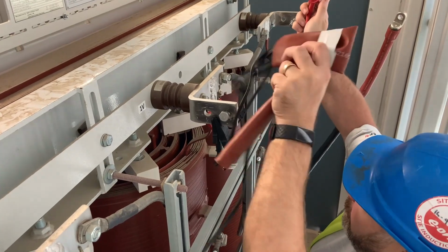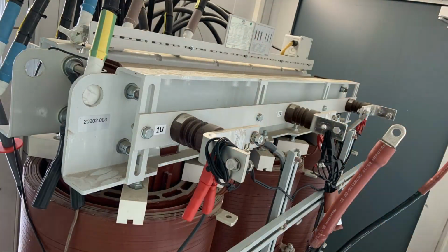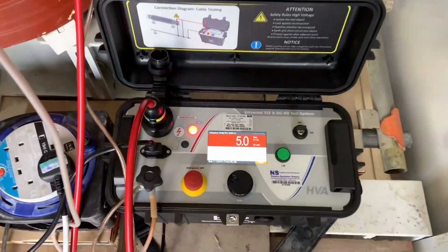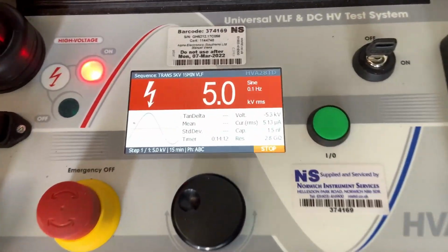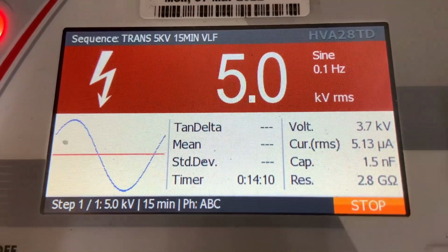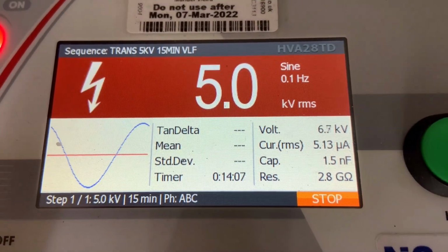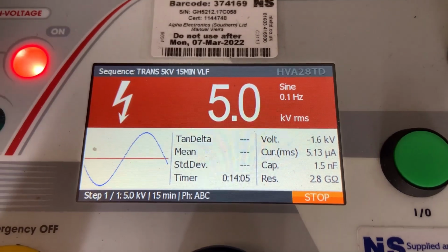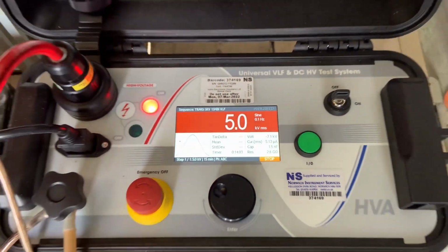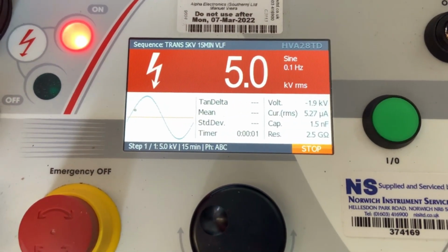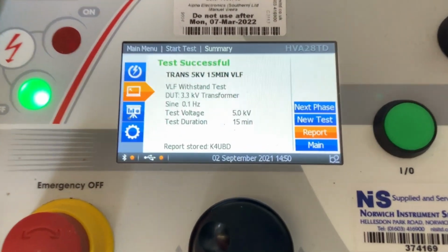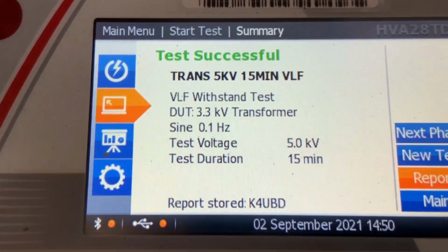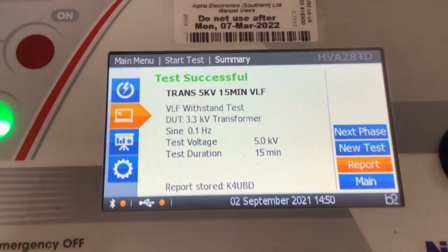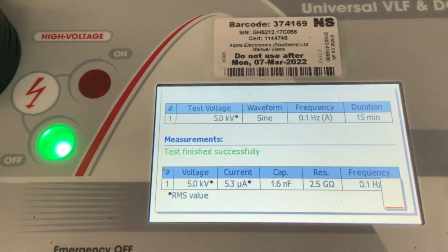Even though the windings of the transformer do create a short for this test, we also put the links in. Okay, test 1, we apply 5 kV VLF. That's very low frequency. 5 kV is the RMS value. We do this for 15 minutes and then we can record the capacitance and the resistance and the leakage current. So this sets the benchmark of any future tests with this installation as is.